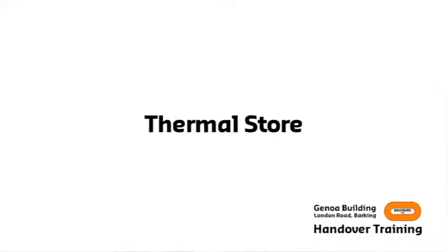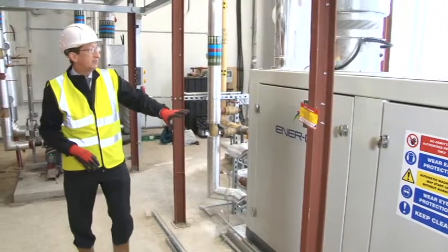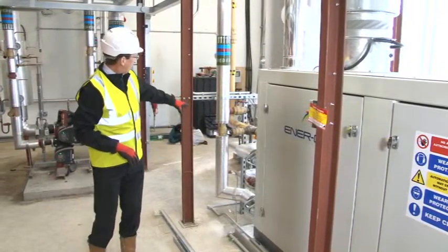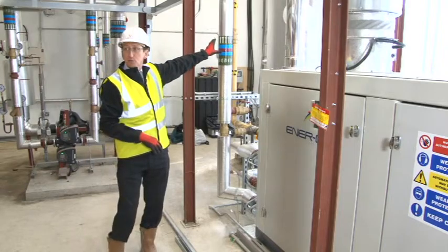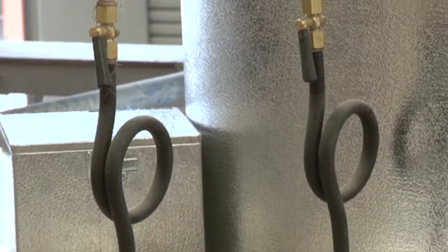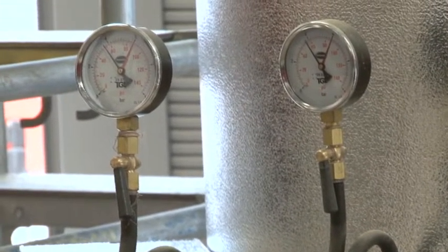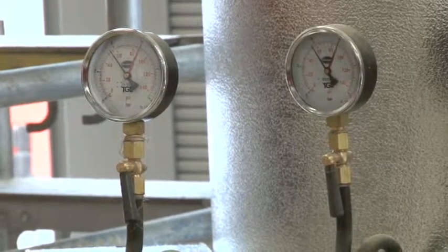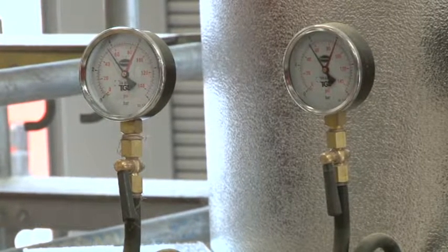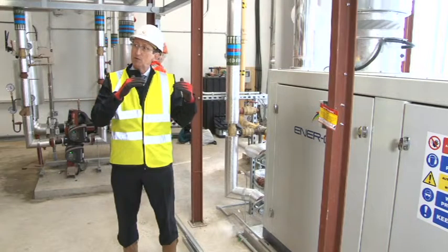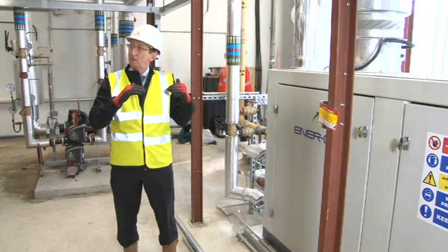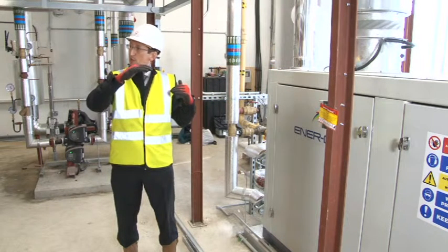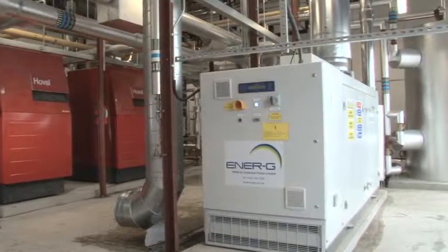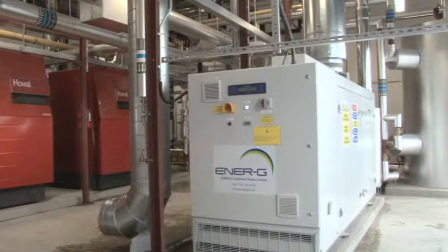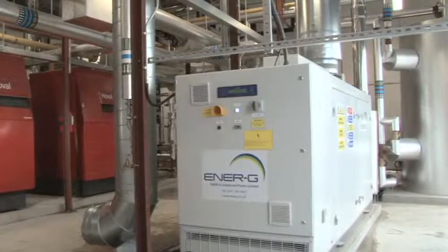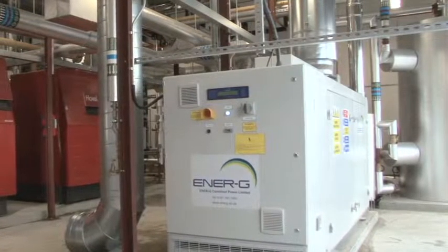Where the heat from the CHP is then supplied is via a set of pumps down here into the large thermal store at the back there. So that's where the heat's collected from the CHP. The reason for the store is so that as heat is generated by it, it's drawn out from the store. But if there's no heat demand for a period of time, you can still go on heating up the thermal store, keep running the engine for as long as we can. Then as heat's drawn away again, it will draw down on the thermal store and we can keep the CHP running for as long as possible.